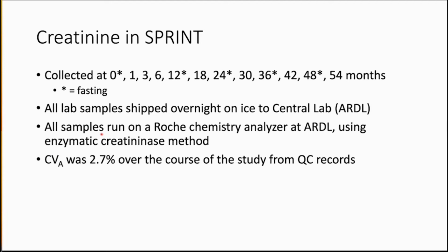We did actually switch instruments during the middle of the trial, but the analytical methodology in terms of reagents and whatnot stayed the same. So it was pretty consistent for the duration of the trial, and it was using an enzymatic creatinine method. And looking back over the analytical quality control records, I was able to establish that the analytical CV for creatinine during the course of the trial was 2.7%, which is sort of expected.